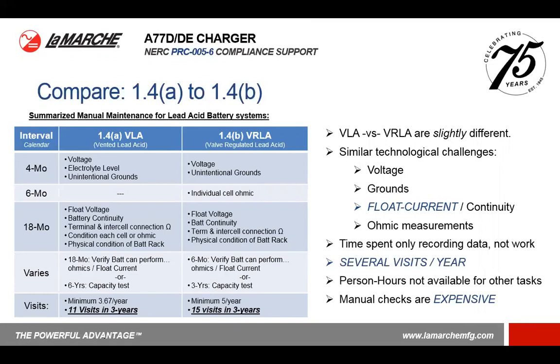This time that's spent recording this is really not even the maintenance data that's being done. It's just recording the data. A full documentation system is required for the NERC auditor and NERC compliance. Ultimately, you must be able to demonstrate to the auditor that this work has been done at the prescribed maintenance intervals. So this involves several visits per year and several person hours that are not available for other tasks to be done. Not only that, this doesn't even mention how many hours are spent recording this data in a database to be able to verify to an auditor that the work has been done. So manual checks are very expensive to do.